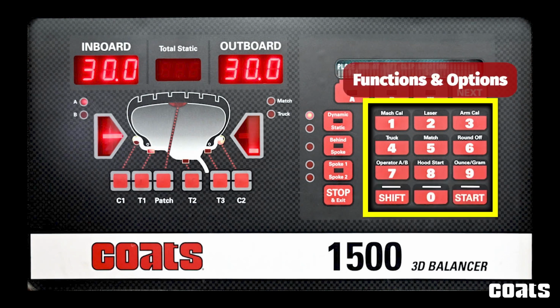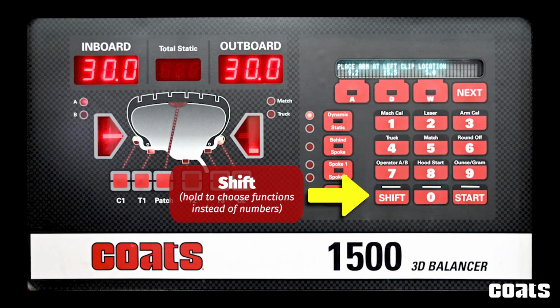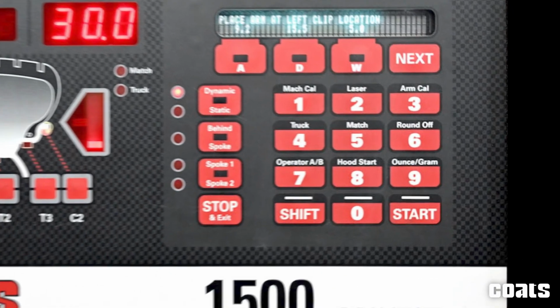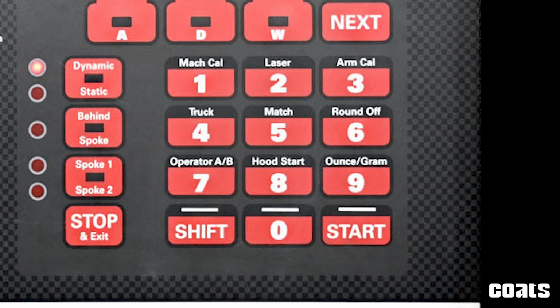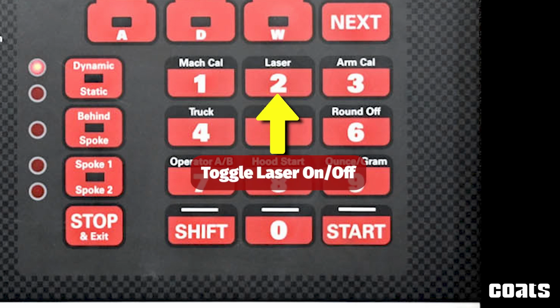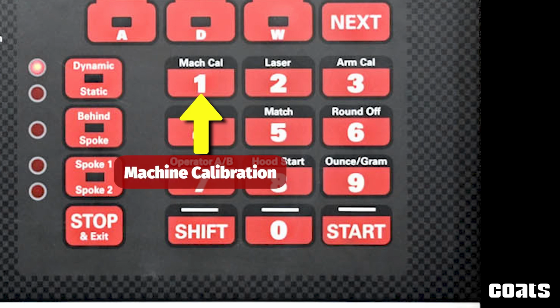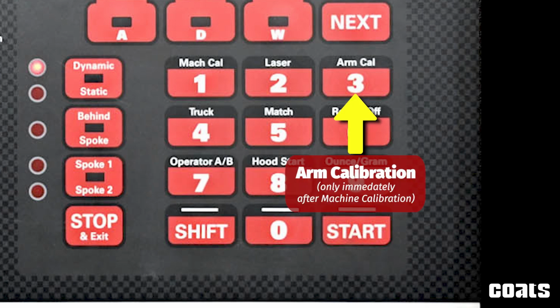This next row of buttons here on this keypad are various functions that you can call up. The shift button here allows you to get to the secondary function, whether in this case it's laser or the truck mode or match. You need to hold down the shift key in order to get to that function. Holding down the shift key and hitting laser will automatically toggle the laser on and off. Holding down the shift key and number 1 allows you to get into the calibration submenu. Holding down shift and number 3 allows you to get to the arm calibration menu.